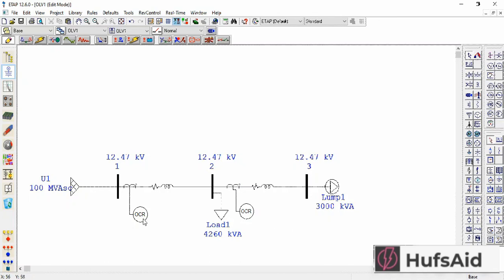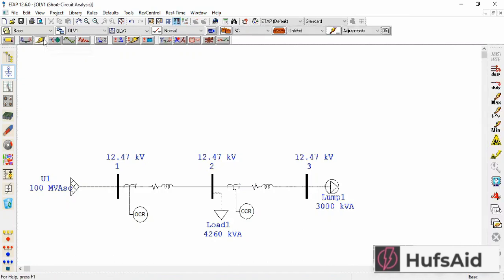Now for the pickup current of the OCR, I'll have to do fault analysis. I will find the fault current by putting a fault on Bus 2, and then I will repeat the same for Bus 3. When the fault is at Bus 3, only the latter portion would be opened. When the fault is at Bus 2, the former portion will be opened and the whole system will be protected in this way.